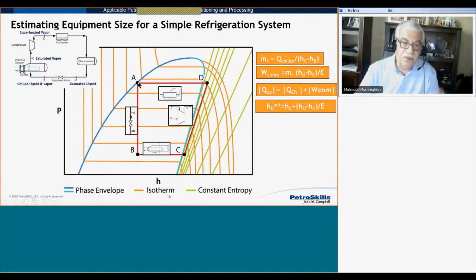So saturated liquid, I'm entering the JT valve, expansion valve. In the JT valve, enthalpy remains the same. So with constant enthalpy, I go down. How far should I go down till I reach the chiller temperature? So I know my chiller temperature of -4 degrees Fahrenheit. I draw a horizontal line and extend it here, and I can read the pressure on the y-axis to be about 36 psi.